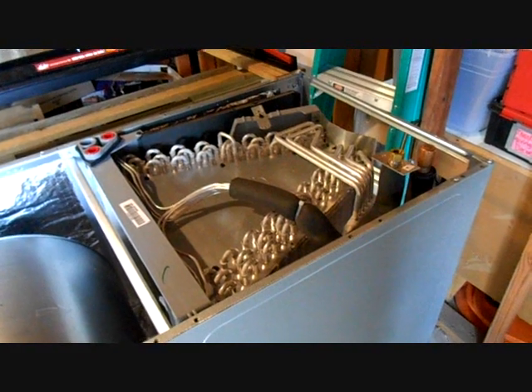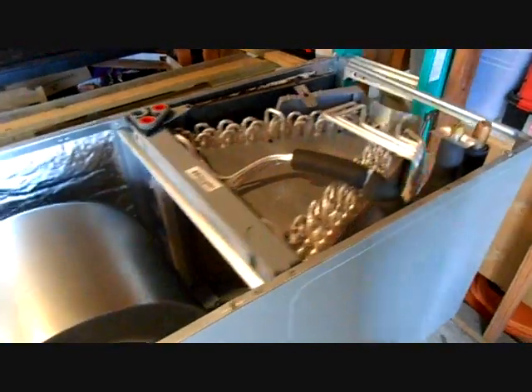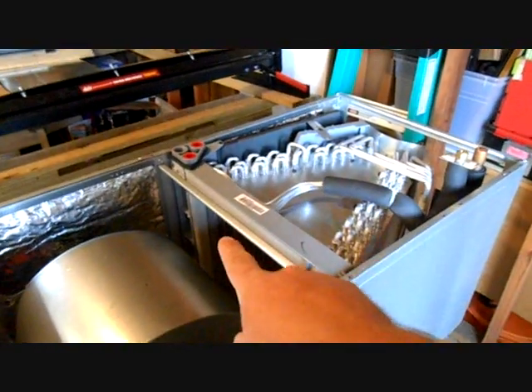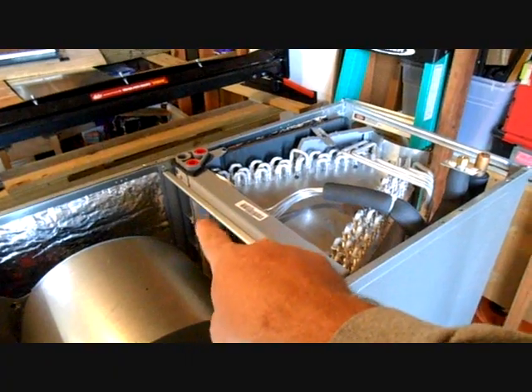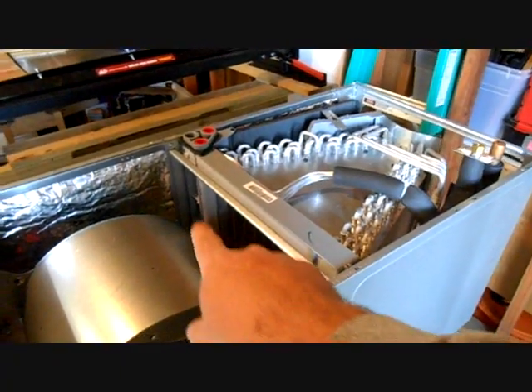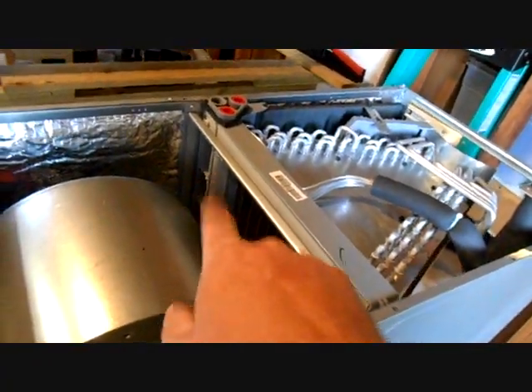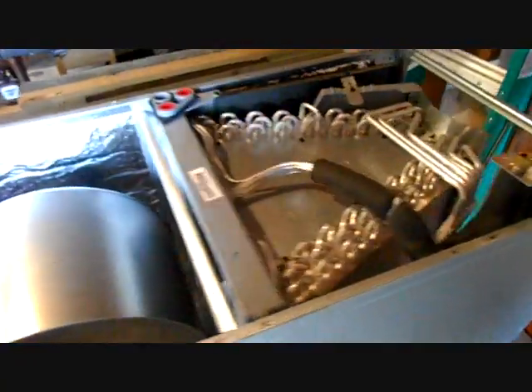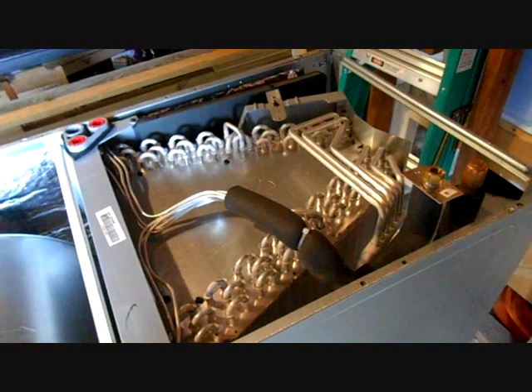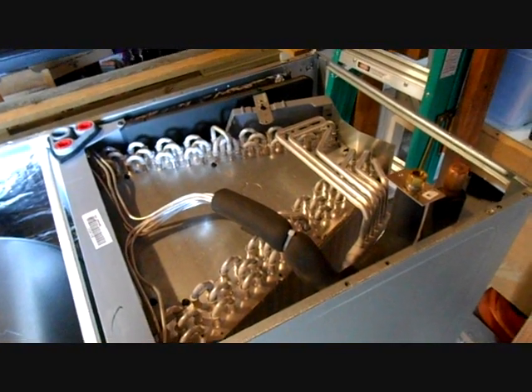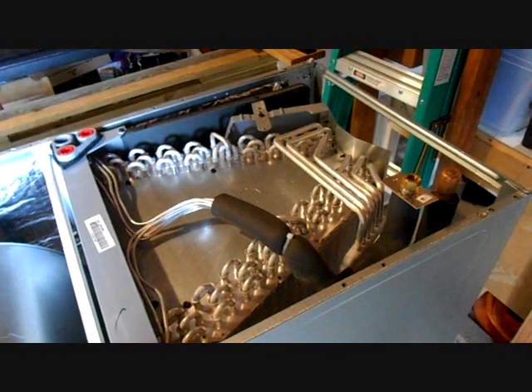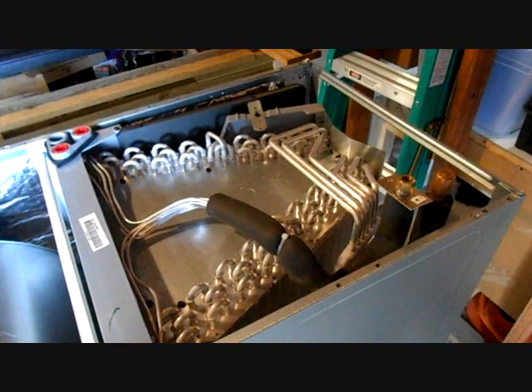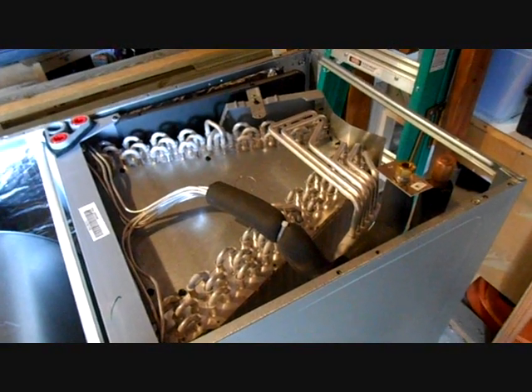On this particular air handler, and most of Goodman's air handlers, if you do down flow, you have to insulate the drain pan on the bottom. That's what I've done here. It's hard to see. There's insulation on the drain pan. And it basically is like foam tape. They sell little packets of it, but usually I just kind of use my own.